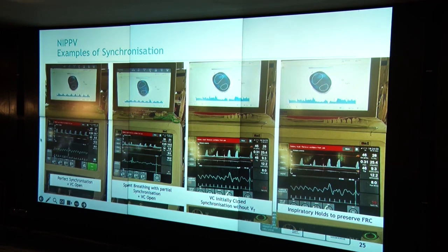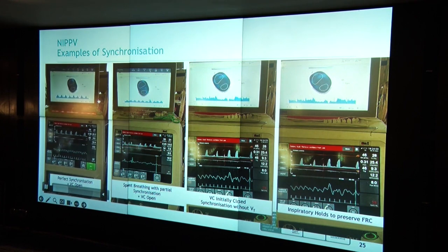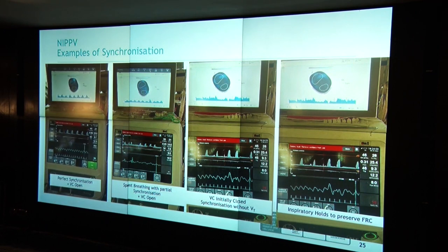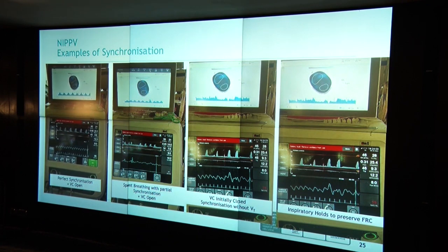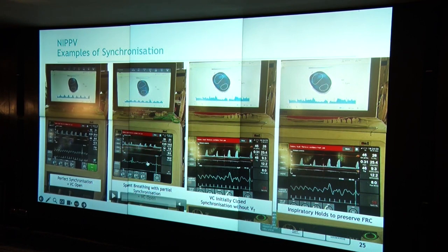You'll see here that every breath is synchronized, every pressure is synchronized, and you'll be able to see that when the pressure wave occurs, very fast, the volume wave goes up. So synchronized wave, synchronized pressure, vocal cord open, gas exchange, tidal ventilation occurring, which is what we all expect to happen.